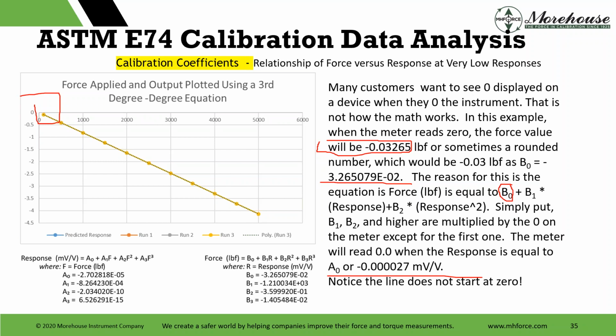So, and if you notice, the line doesn't start at 0. So therefore, your device is probably not going to read right for the first 10 pounds on this load cell. Really, we didn't start the calibration till 100, so you can't trust it. You cannot trust any reading below 100. But at 100, it darn well better read what the calibration reports it says it's going to read. And that's going to be within whatever, it's going to read plus or minus whatever the lower limit factor is.